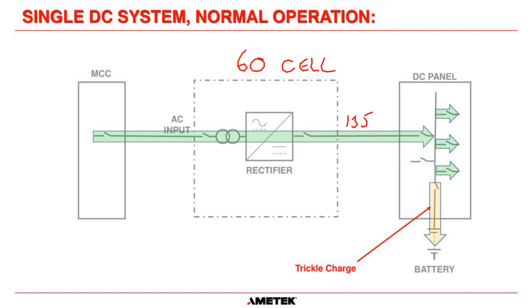Now, the open string voltage of a battery of 60 cells is going to be around 128 volts DC. So you can see that 135 volts is more positive than 128 volts. So that's why the charger feeds the load circuits. It's just through design and the requirements of charging lead acid batteries. And then obviously we have a small amount of trickle charge current going to the battery to maintain their charge.